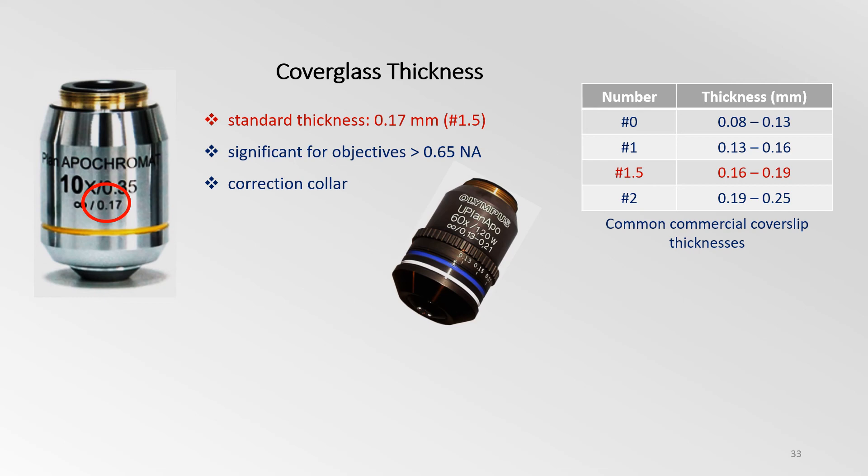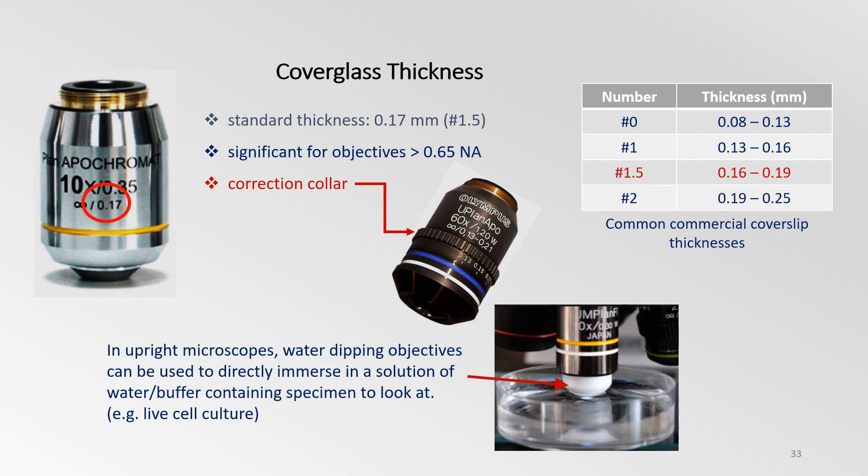Therefore, some more advanced objectives possess a correction collar or ring that can be turned to adjust the objective to the actual cover glass thickness which is in use. Water dipping lenses eliminate the need for coverslips. These objectives can be directly immersed in the solution of water which contains the specimens to look at.